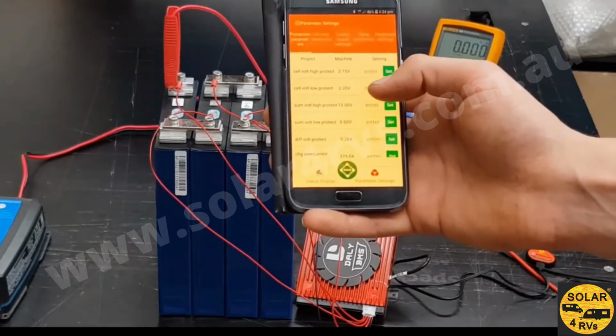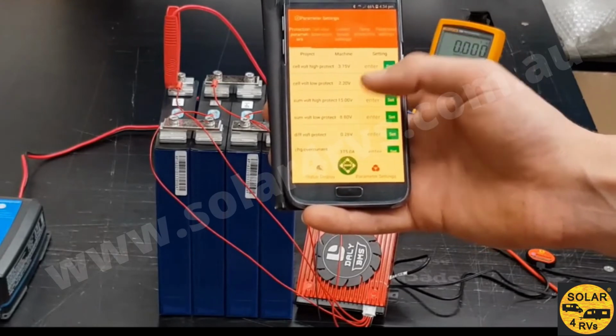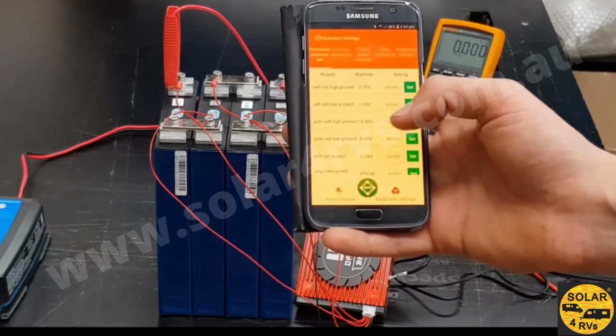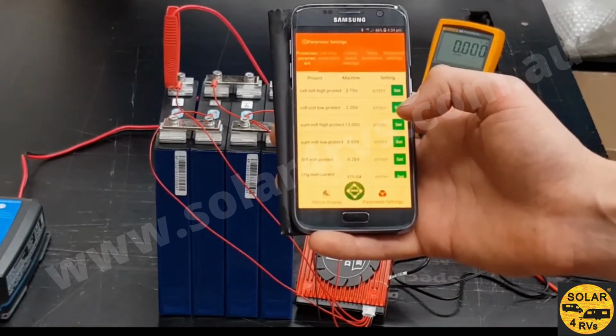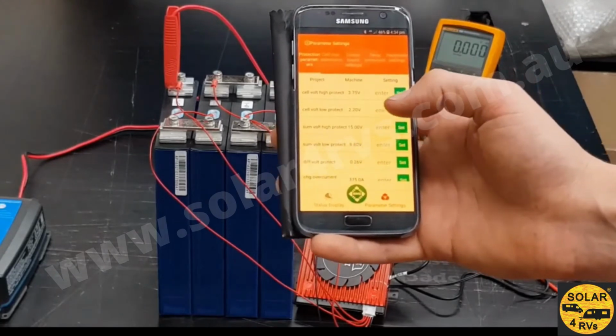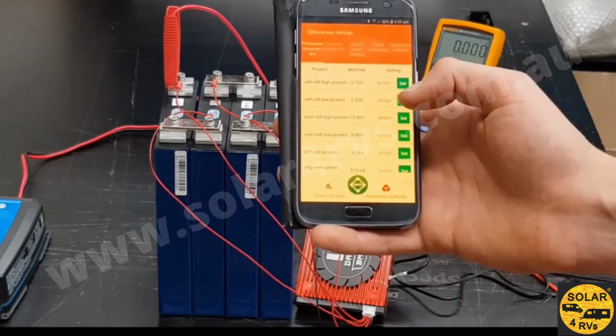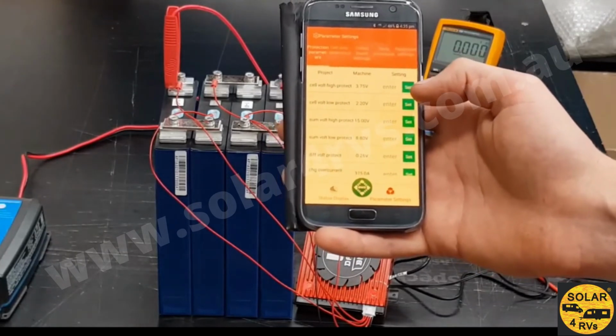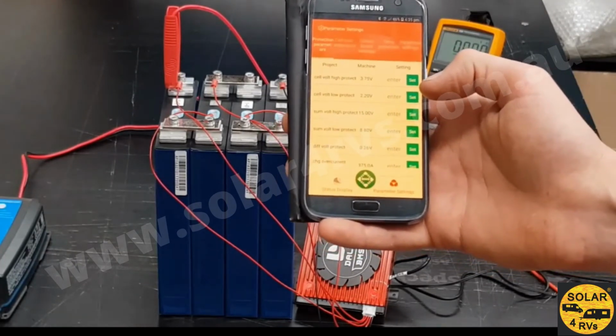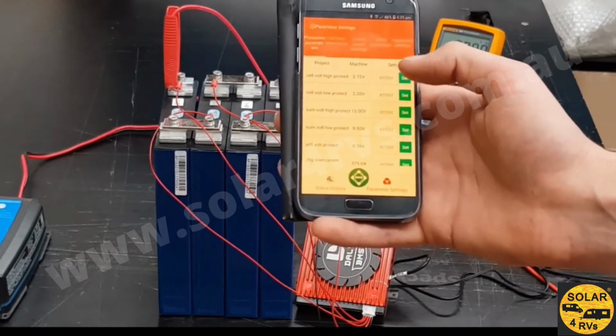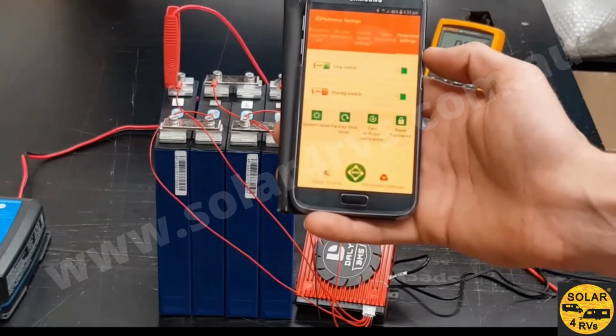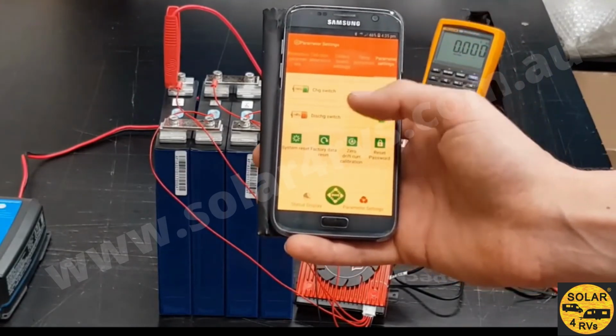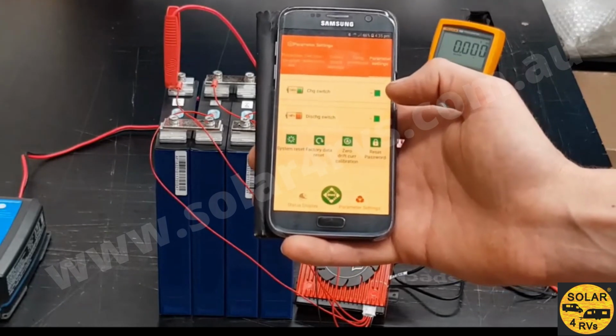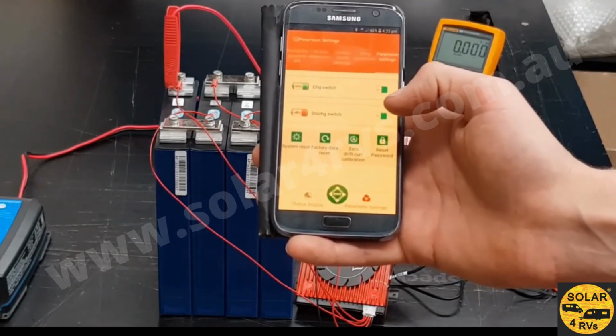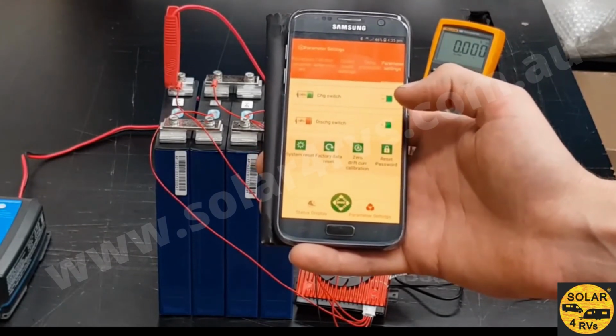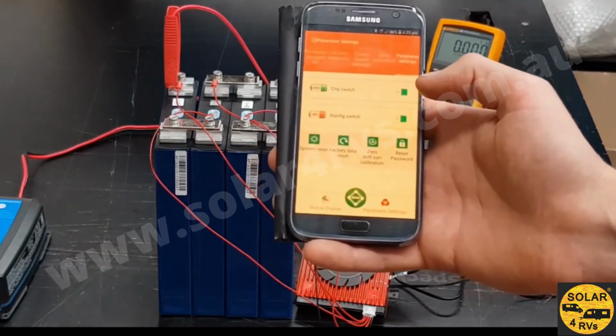I don't recommend changing these set points in the app itself though. I recommend changing them in the PC software and referencing your cell manufacturer's data sheet. That's because in the app you can see the trip points, but you can't see the reset points. So normally if you change a trip point, you would correspondingly change the reset point. The other note is that the parameter switches don't work on the 3 and 4S units, but they will work on the 5 to 32S Daly units.